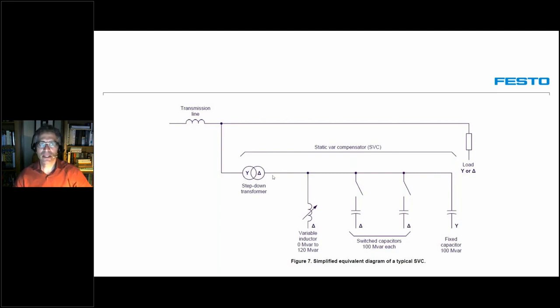First of all, the SVC will be connected to the transmission line through a step-down transformer, because it would be much too hard in terms of electronics to manage 100 kilovolts directly. So we step down the voltage from the transmission line to be manageable by the SVC, through a transformer connected in Y-delta, with the primary in Y and the secondary in delta, to eliminate as much as possible the third harmonics produced by our static VAR compensator. That's one of the reasons we use this star-delta connection.